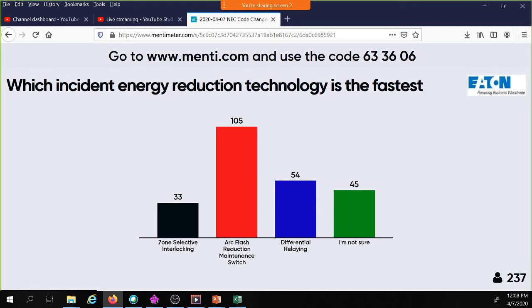The moment it became an instinct, the moment I did it so often that I would turn that safety off, turn it back on again, and it would just be instinct, my brain wasn't as engaged and it was a much faster response. The same thing applies with an overcurrent protective device. The arc reduction maintenance switch is an analog circuit. There's no brain in the picture.